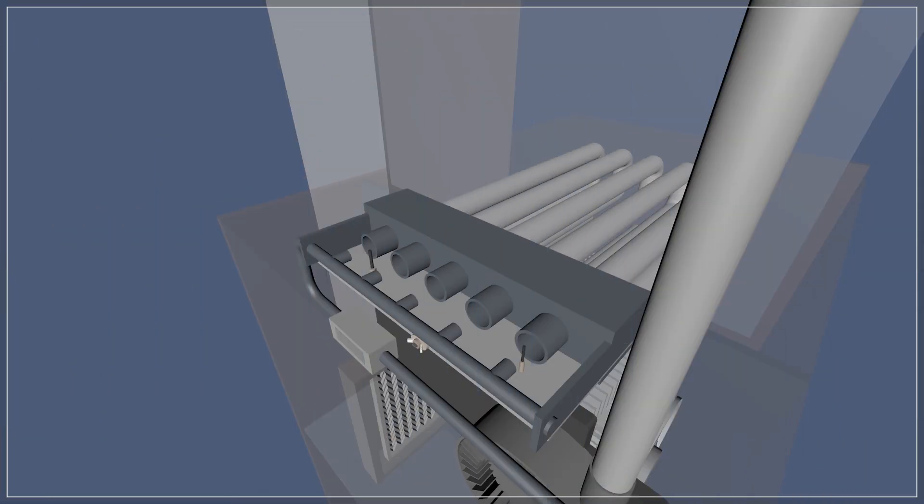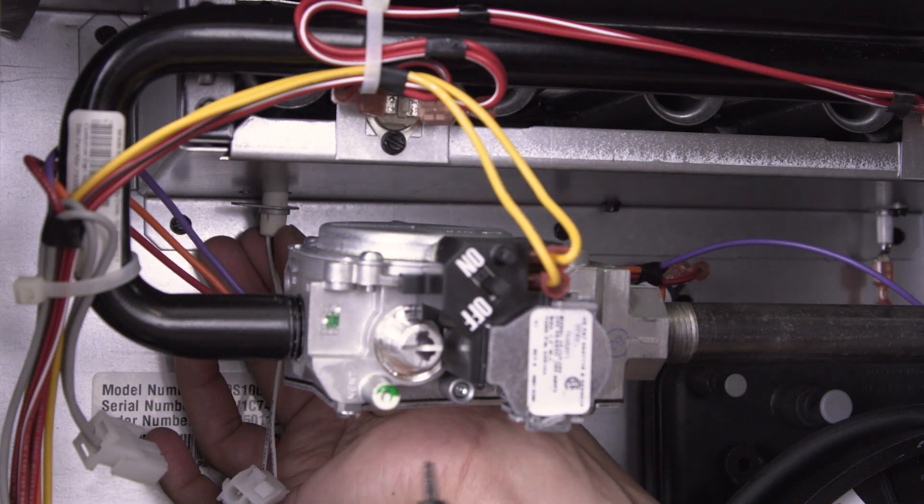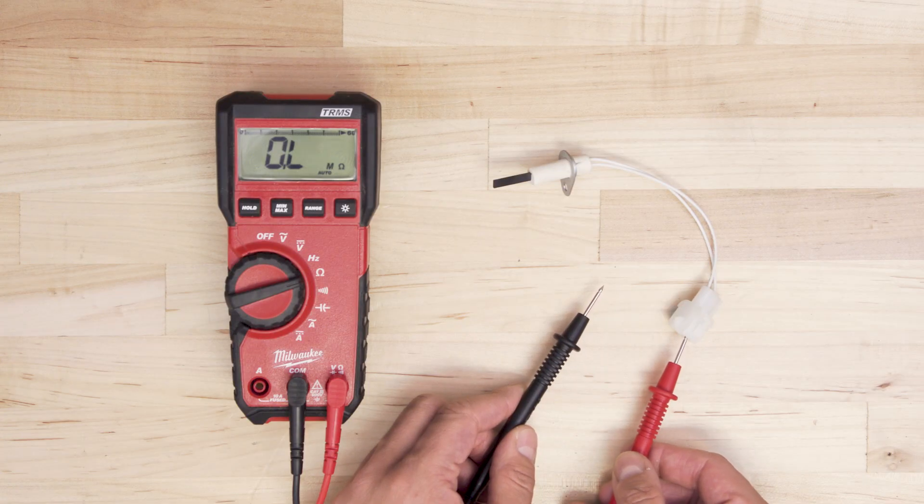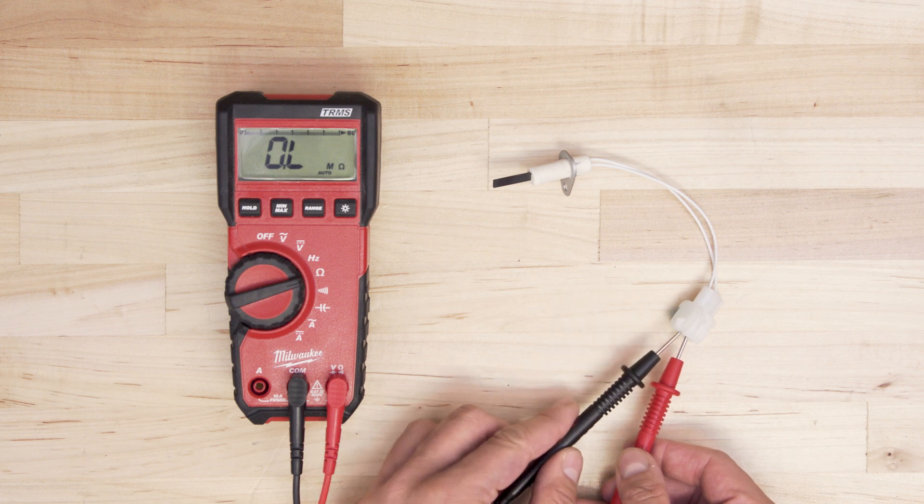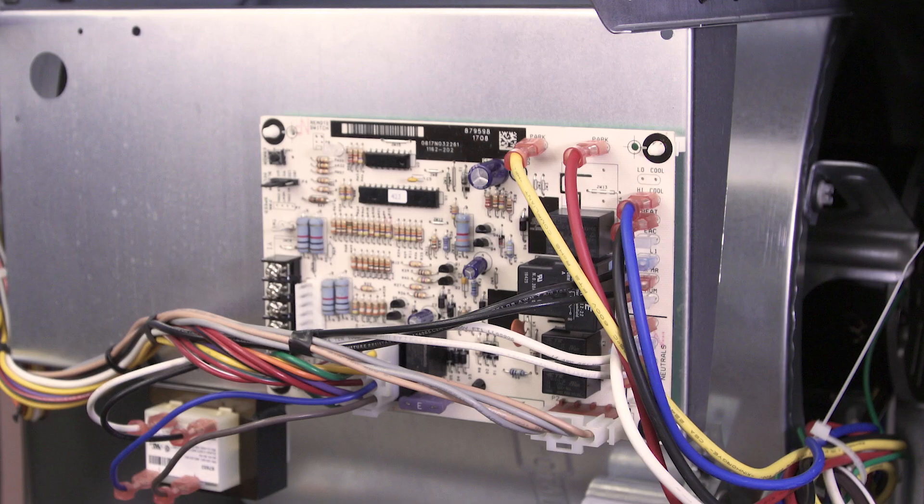If the pressure is good, then voltage is sent to the hot surface igniter. Some furnaces might use a spark igniter instead. If the igniter doesn't activate, then remove the igniter and test for continuity. If the igniter doesn't have continuity, it will need to be replaced. If the igniter has continuity but still doesn't ignite, then it might be a problem with the wires or the control board.